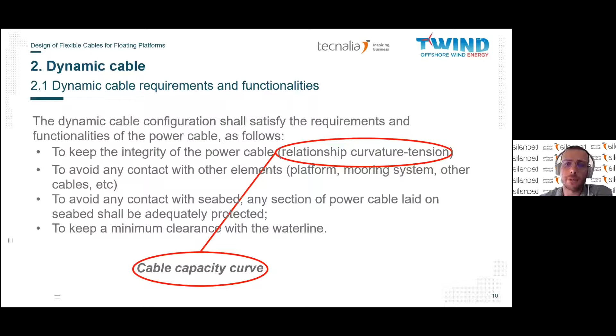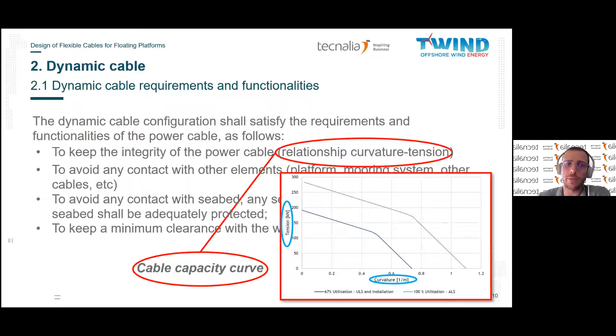The relationship between curvature and tension is the most important characteristic of the power cable that the designer needs. It's called the cable capacity curve. It's a curve that shows the relationship between tension and curvature. Normally there is a different curve for each design condition. In this example, there is one for ultimate limit states and installation, and another one for accidental limit states. The most important fact is that this curve is fundamental for the design, and it's provided only by the cable manufacturer. And normally the designer gets the cable capacity curve only after the purchase of the cable.